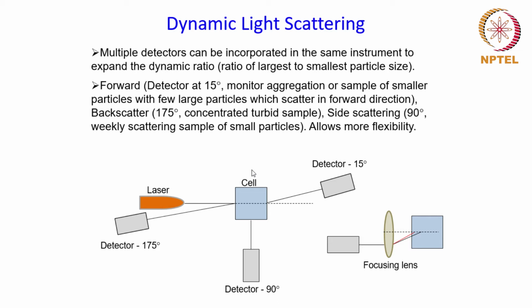For example, if there is a dilute sample of small particles, there may be a need to have more scattering from each of these particles, and therefore it may be beneficial to increase the path length, and therefore the focus point can be changed to a larger distance.